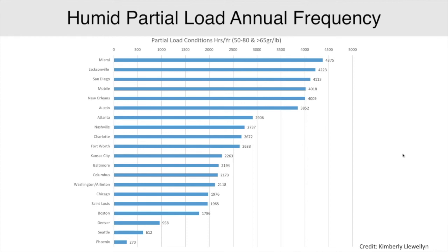This is a chart that a good friend of mine, Kimberly Llewellyn with Mitsubishi, put together, and basically this is showing us all the partial load conditions throughout the year where we're at that 50 to 80 degree temperature range and a 50 or a higher degree dew point. So I think this is above a 55 degree dew point here. So Miami, I mean, we got over 4,300 hours in a year that we're at these partial load conditions with really high outdoor dew points. Jacksonville, I mean, even Phoenix, down at the way bottom, we get that monsoon season. So these are all the hours in the year in these locations that we are not running at peak load, and we're going to have to figure out how we're going to control that humidity and figure out what size dehumidifier we're going to need in order to be able to control that.